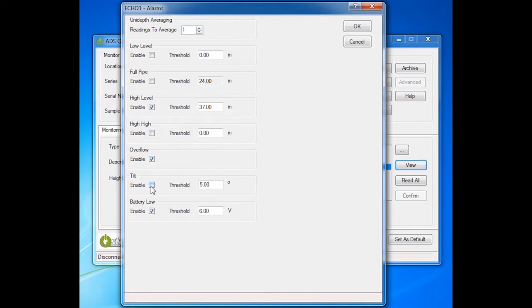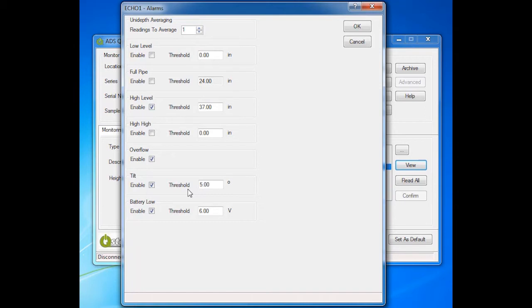For Tilt, check Enable and leave the threshold at the default value of 5 degrees. The Echo will trigger a tilt alarm when the Echo is not level, when there is a change in orientation over the threshold. Note that while the Echo is in a tilt alarm state, the only alarms that will be initiated are low battery, overflow, or tilt returned to normal. This eliminates false depth alarms.